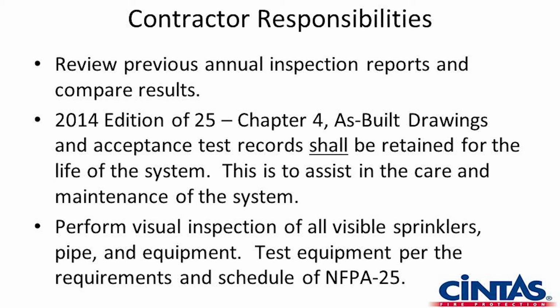The contractor's responsibility is to review the inspection reports and compare the results year after year. When I walk into a riser room to conduct an inspection and there's a stack of tags hanging off the riser, maybe 30 tags, I get excited because I can flip back and see what has been tagged and what has been commented about, even though I don't have the inspection report.